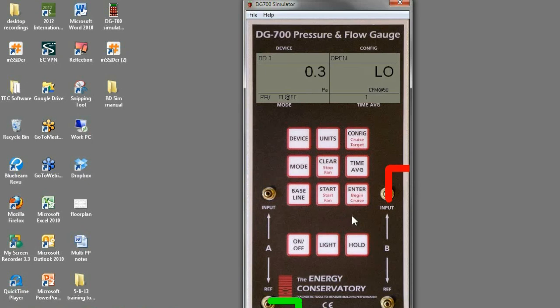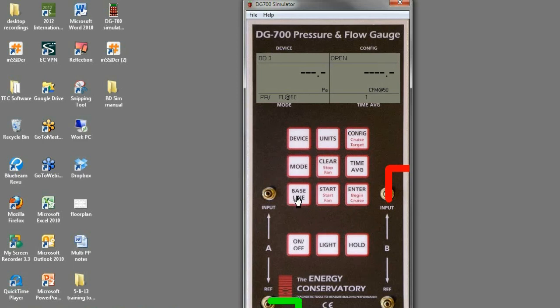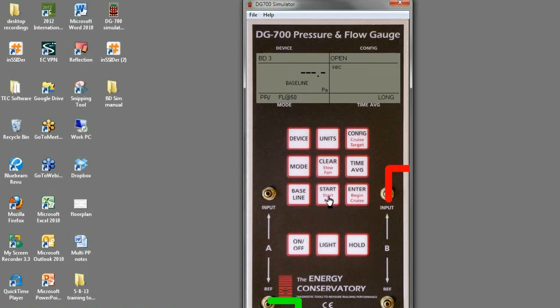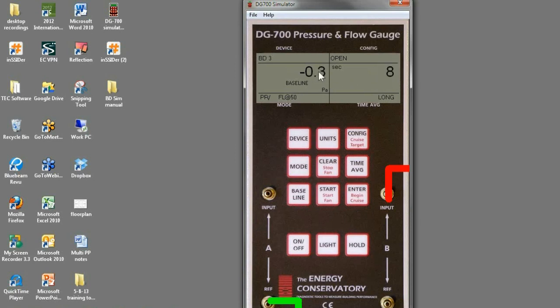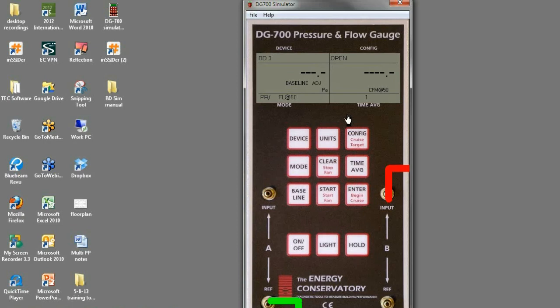You can also use the cruise function of the gauge. Well, let's go through baseline first. You can use the baseline function of the gauge by clicking baseline, and then it will flash baseline on channel A, and then click start. Then the baseline will stay solid, and it'll start counting up in seconds on channel B. And then once this number stabilizes for a few seconds, you can push enter. Now it's entered that baseline adjustment into the gauge.